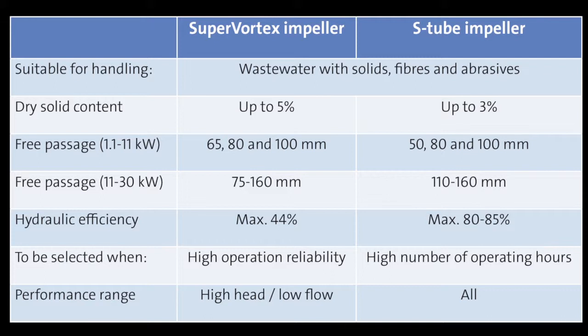Here we have an overview comparing the two impeller types. The conclusion is that you should choose the super vortex impeller when you have a high dry solid content in the wastewater and require high operational reliability. The S-tube impeller you should choose when both non-clogging capabilities and high efficiency are of importance.